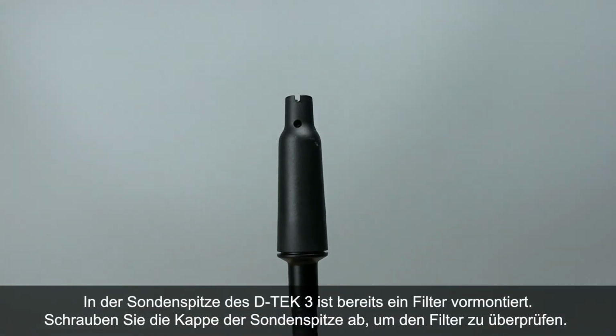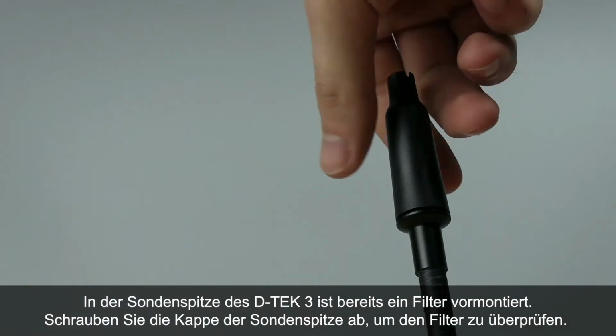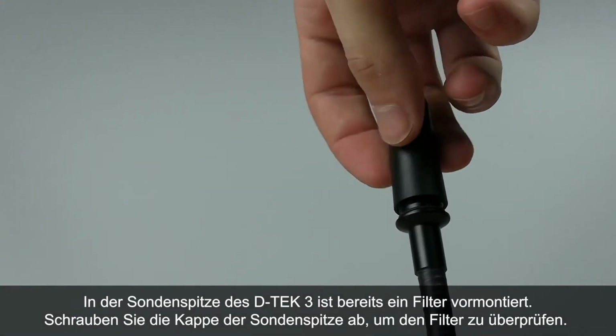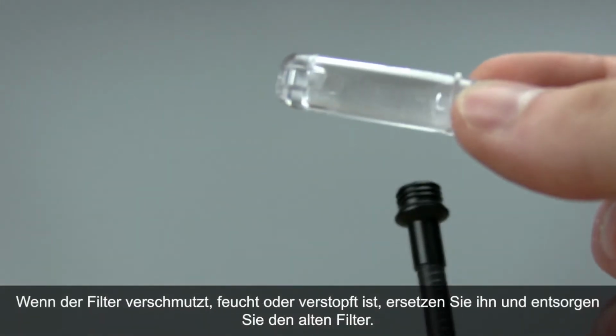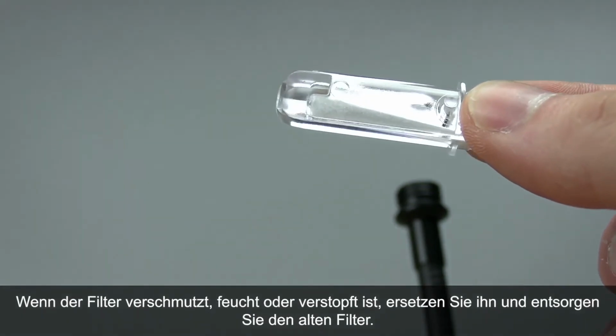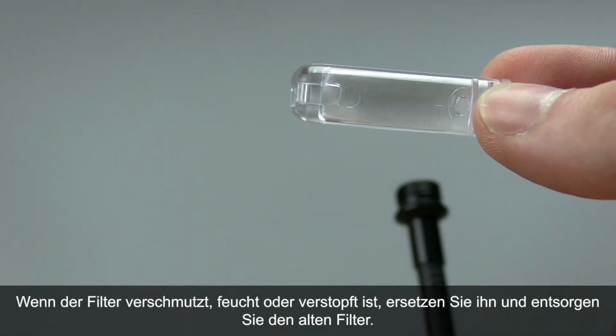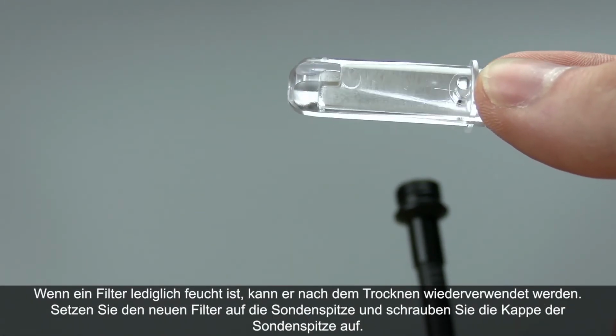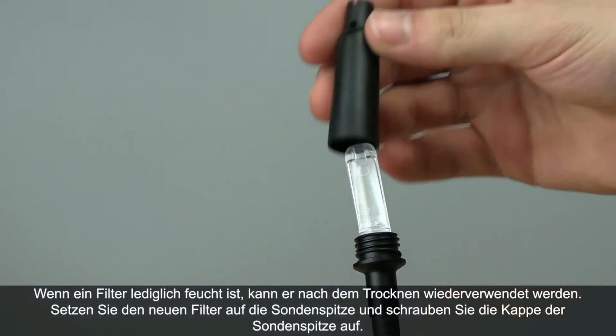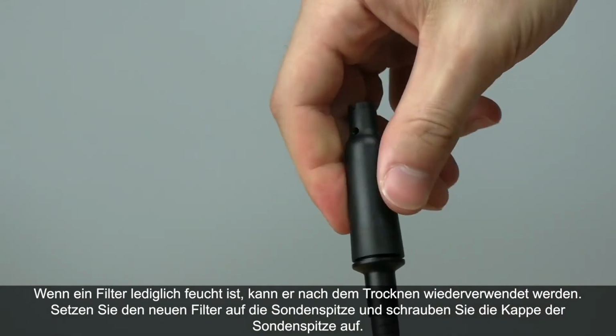A filter is pre-installed in D-TEK-3's probe tip. Unscrew the probe tip cap to check the filter. If the filter looks dirty, gets wet, or clogged, replace and discard the old filter. When a filter is only wet, it can be reused once it dries. Insert the new filter into the probe tip and screw on the probe tip cap.